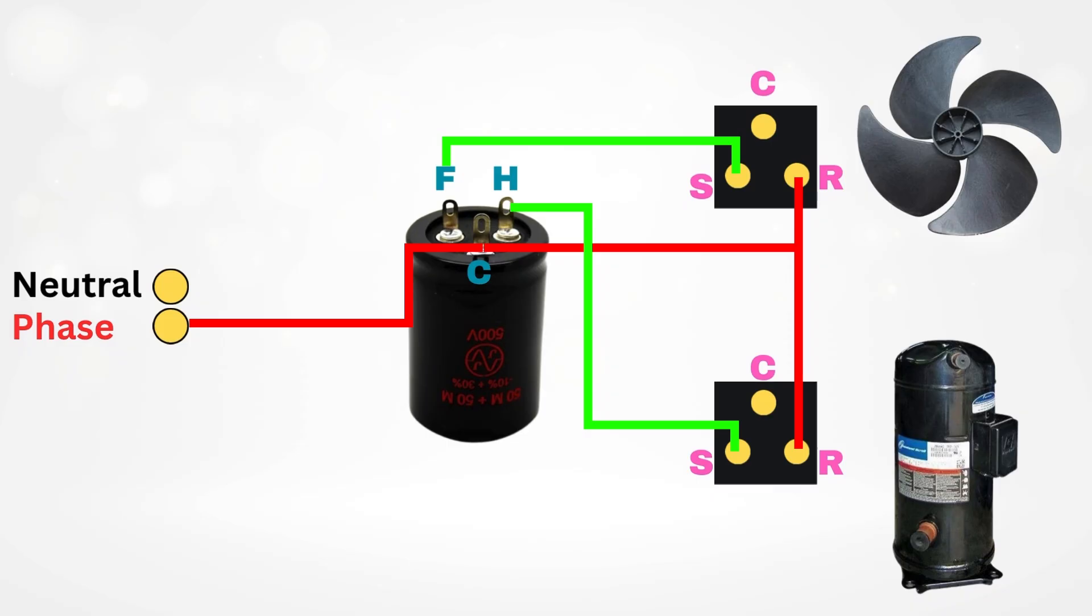Finally, the common wires of both the compressor and fan motor are connected to the neutral of the power supply. This completes the wiring setup. Once the indoor unit sends a signal to the outdoor unit to turn on, the capacitor instantly delivers stored energy to both the fan motor and the compressor through the fan and Herm terminals.